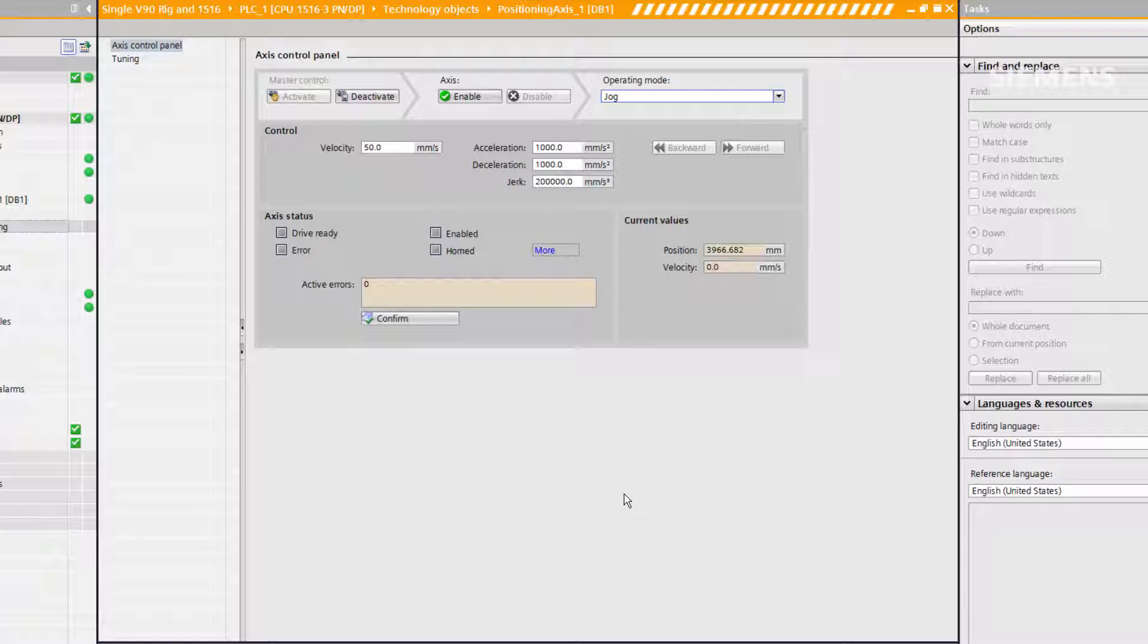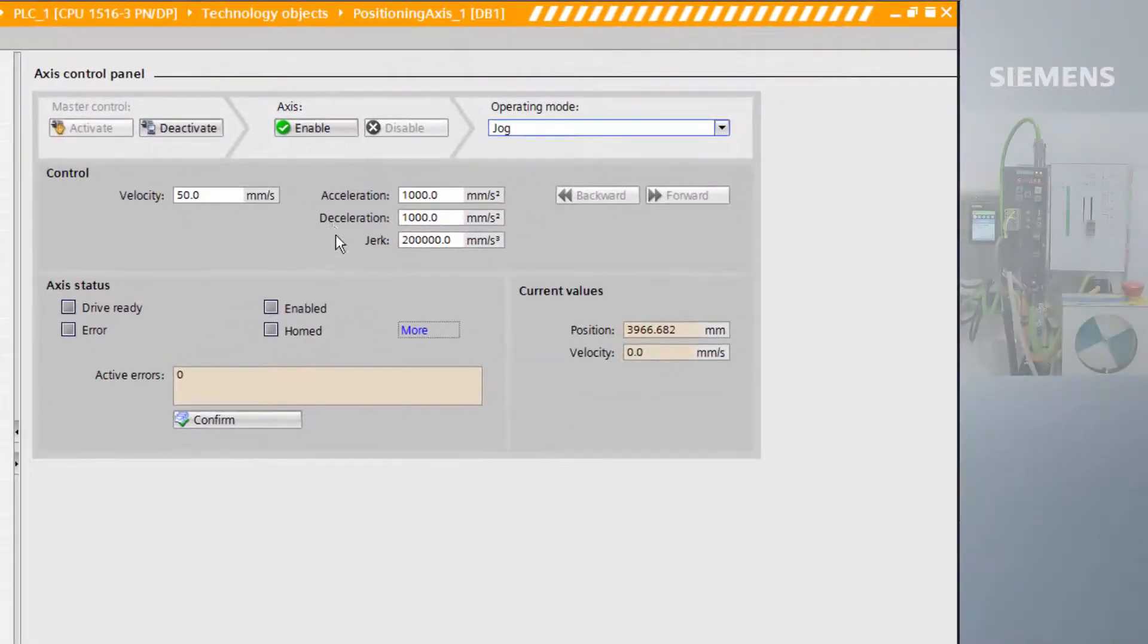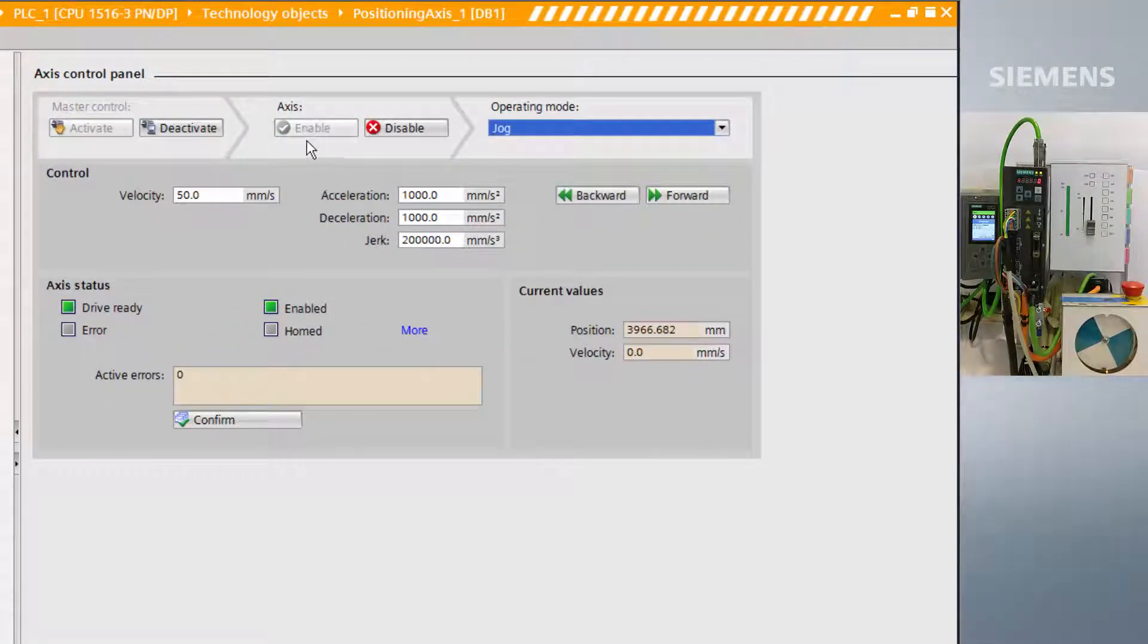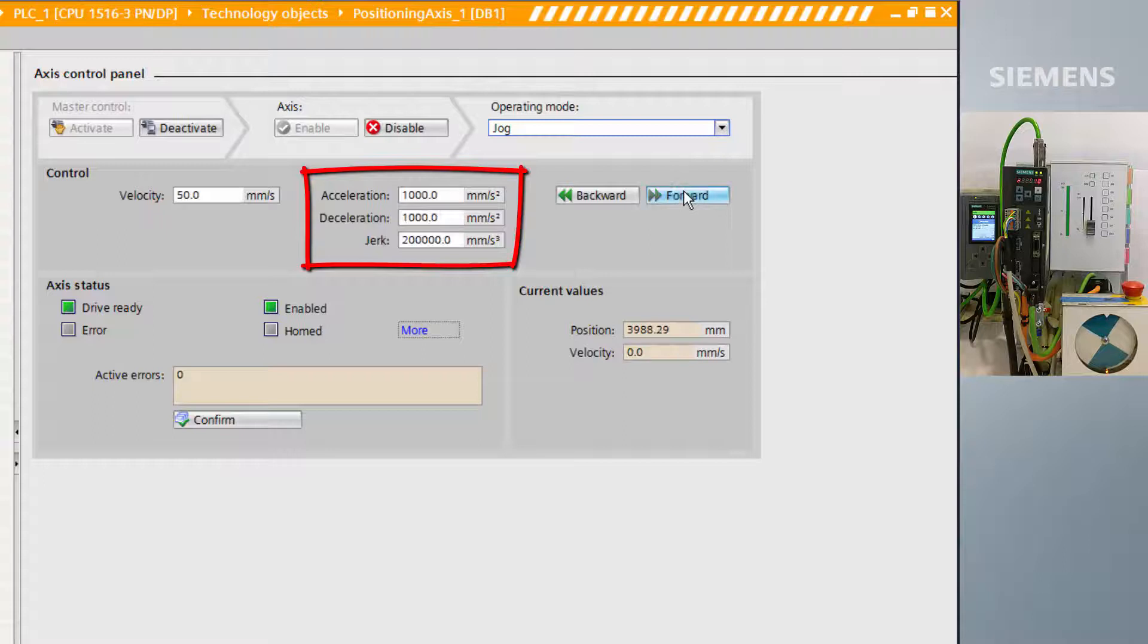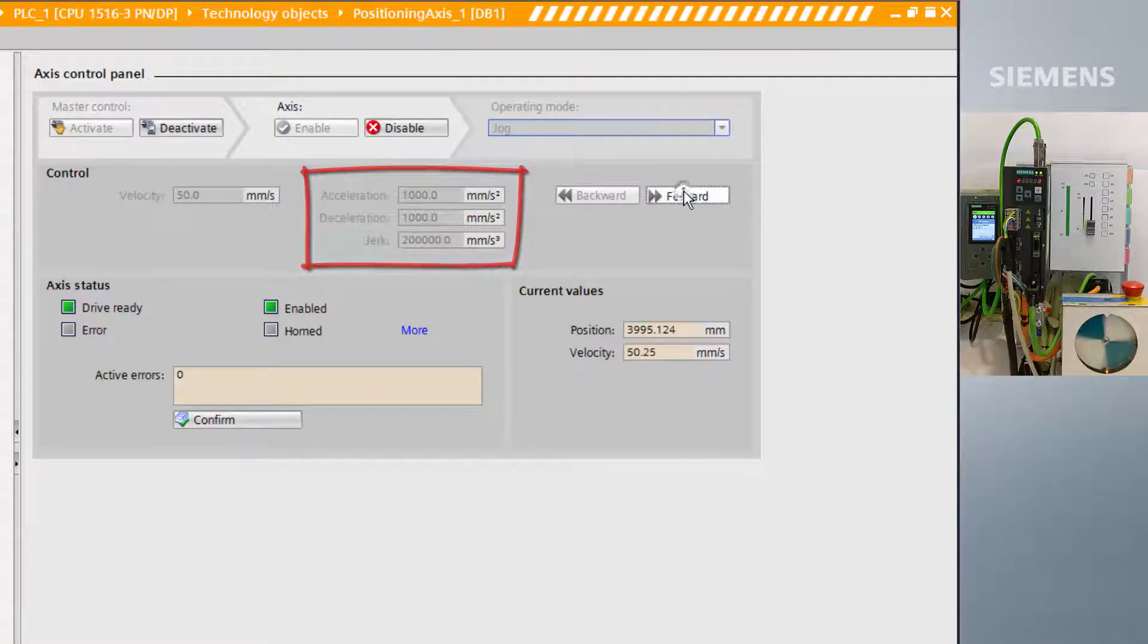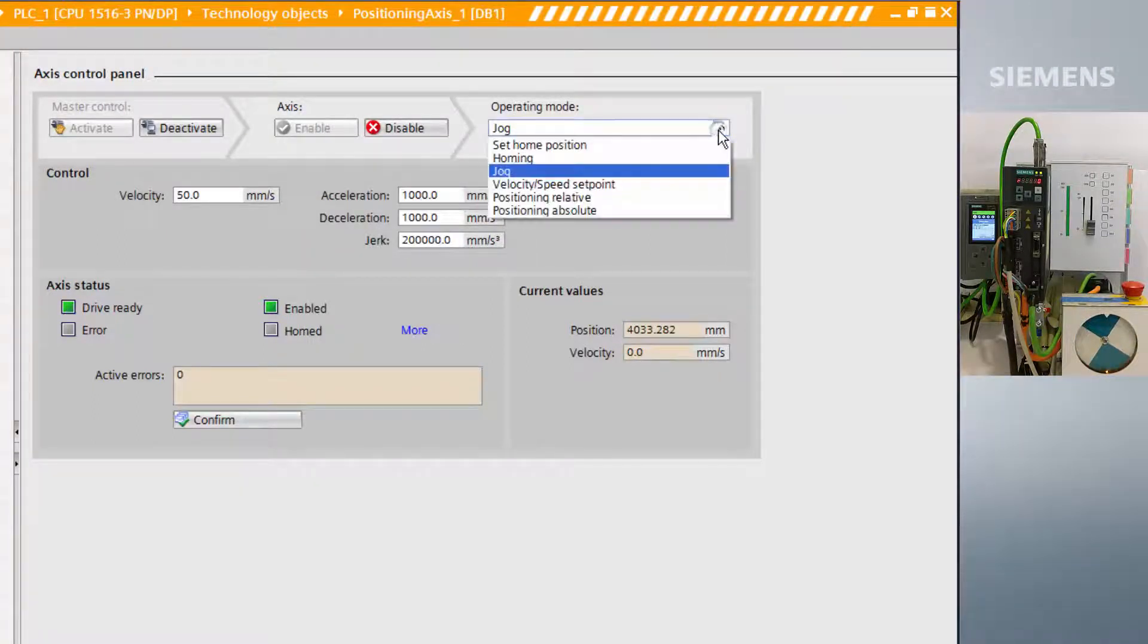From the technology object control panel, we can manually control the positioning loop. We are offered more options than in the drive control panel, such as acceleration, deceleration, and jerk, as well as having many more operating modes, such as homing or positioning relative.